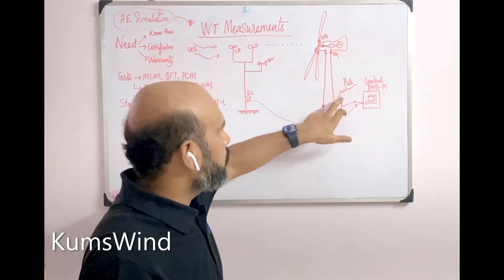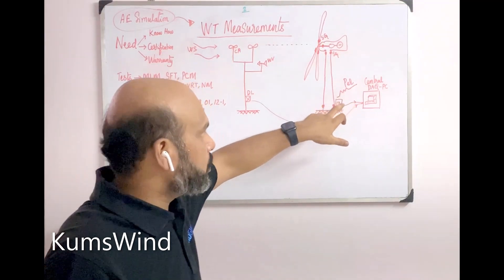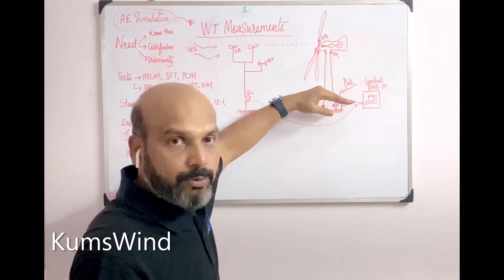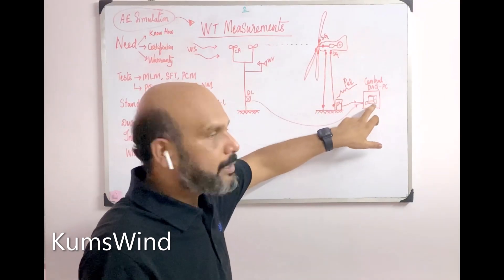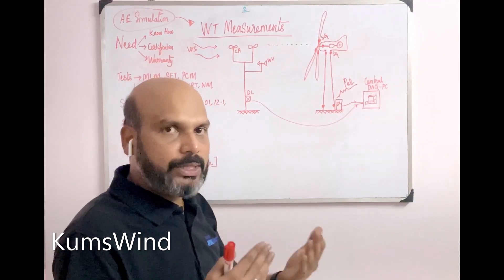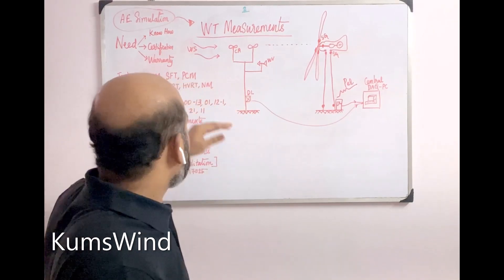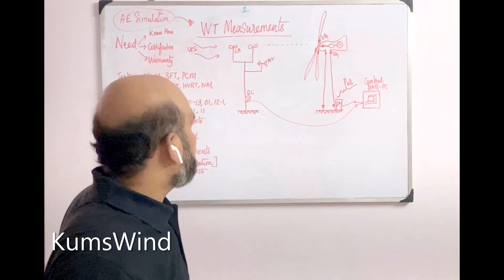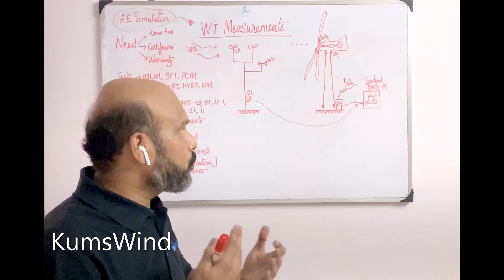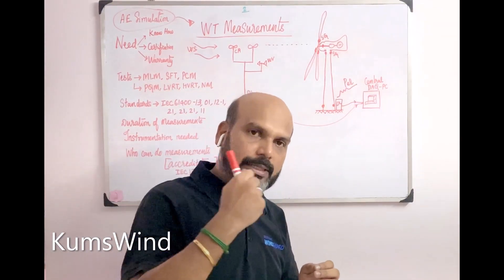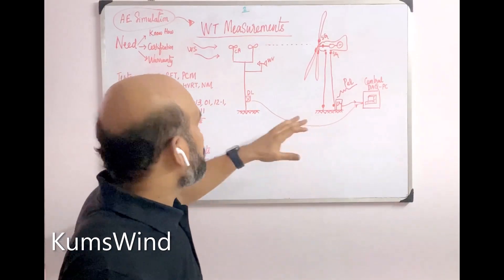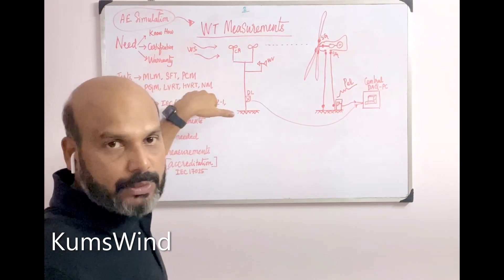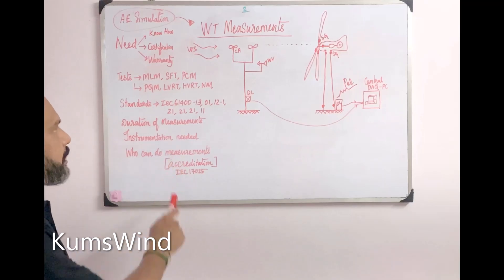Apart from mechanical sensors, current transformers (CTs) and potential transformers (PTs) mounted at the tower bottom measure electrical power, grid frequency, and reactive power produced by the turbine. All sensors are connected to a central PC-based data acquisition system with a high sampling frequency. Sampling requirements vary by measurement: power curve measurements need at least 1 Hz sampling, while power quality measurements require kilohertz-range sampling to capture sudden transients during turbine cut-in and cut-out. Sensor accuracy requirements are also specified in the respective standards.